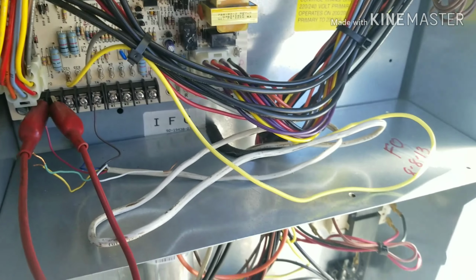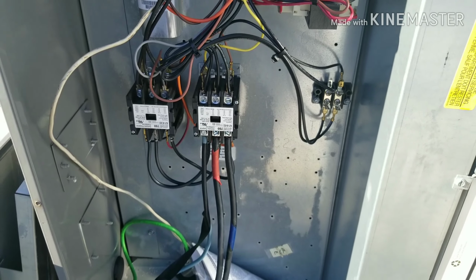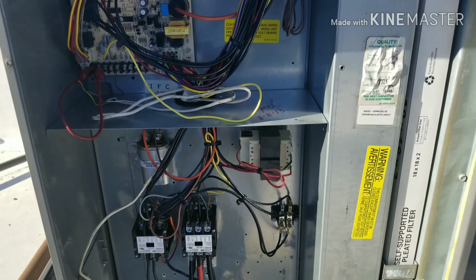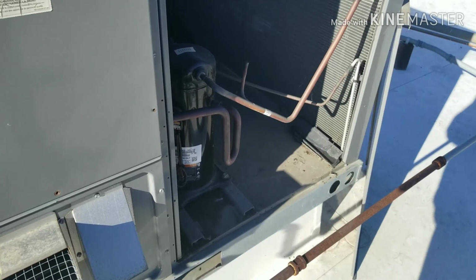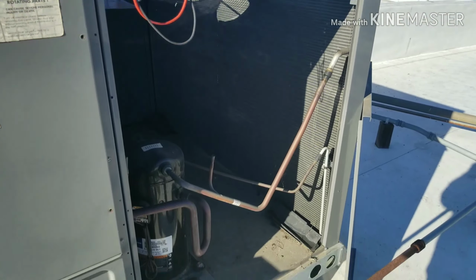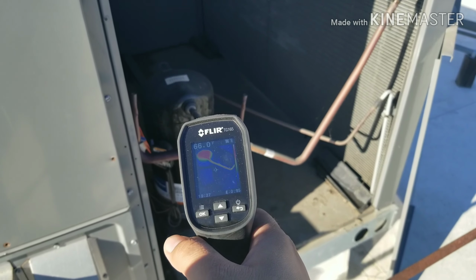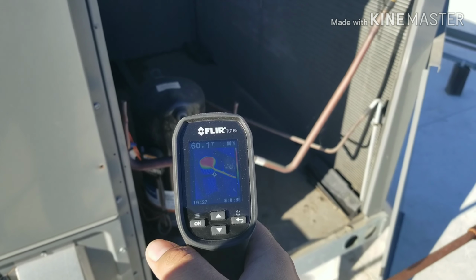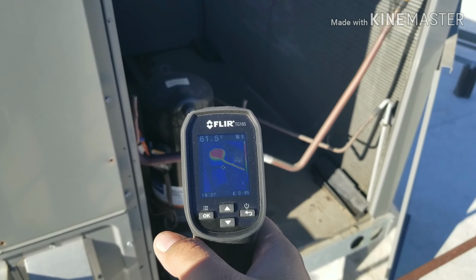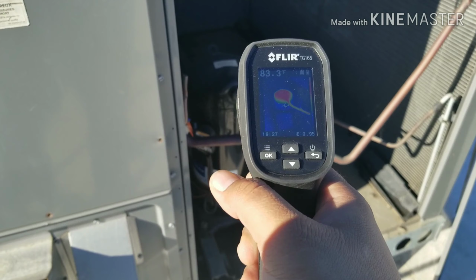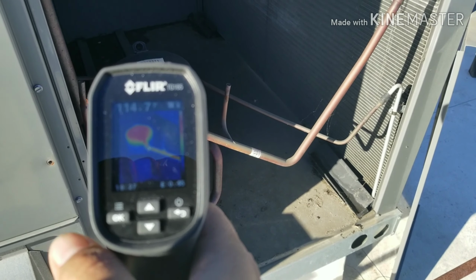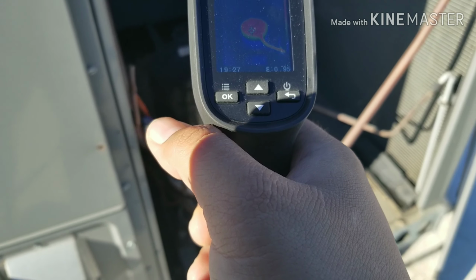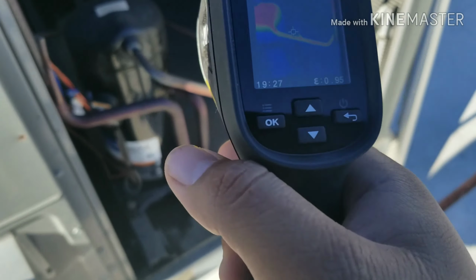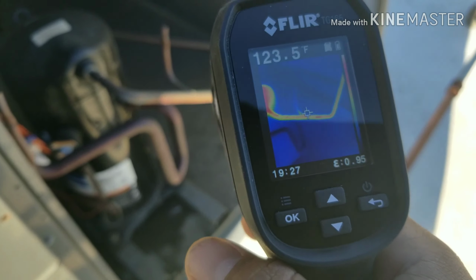So now we got cooling on, contactors are in, so it's not making any sound. The panel off. We got this FLIR thermal imager. Look at the top of the compressor, about 145 degrees. Follow the line. Hopefully you guys can see. Follow that line.